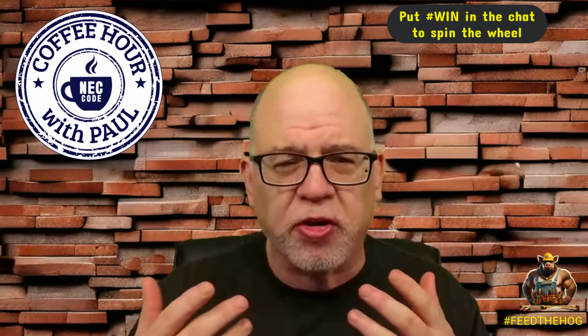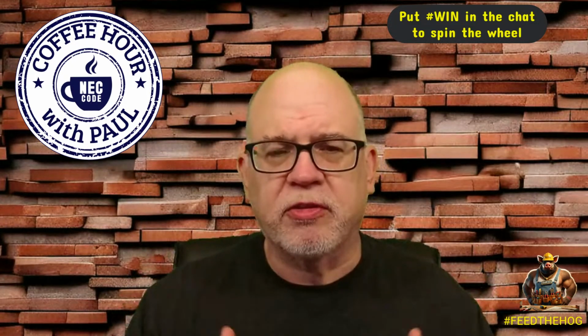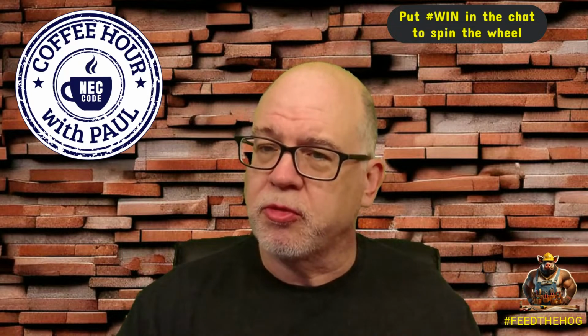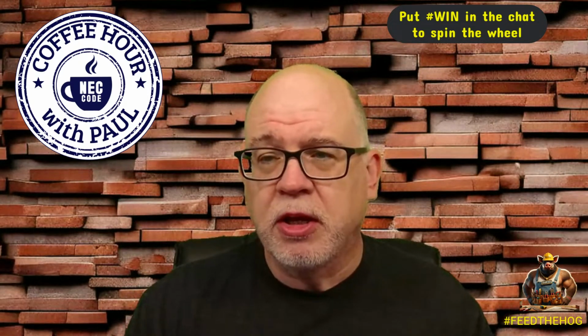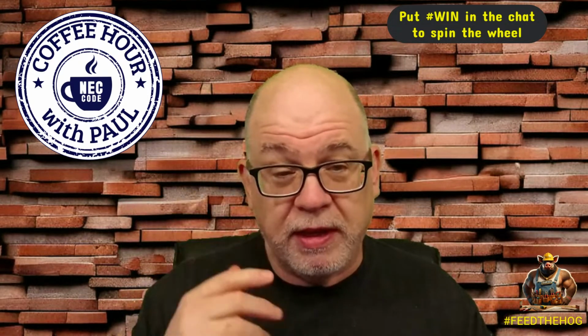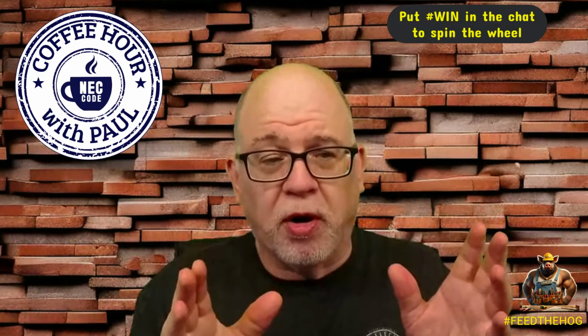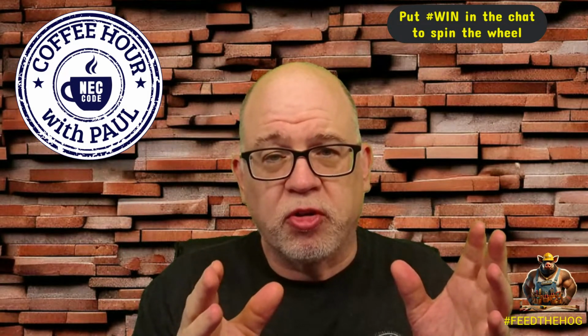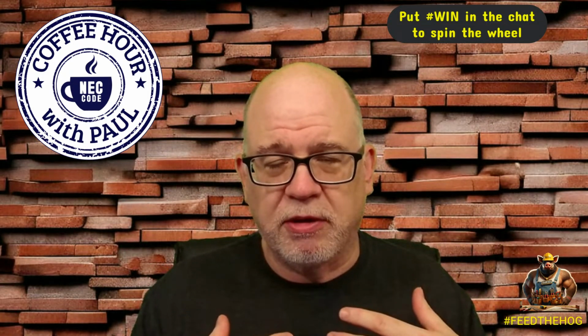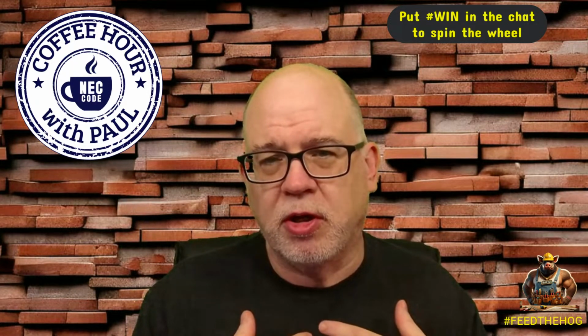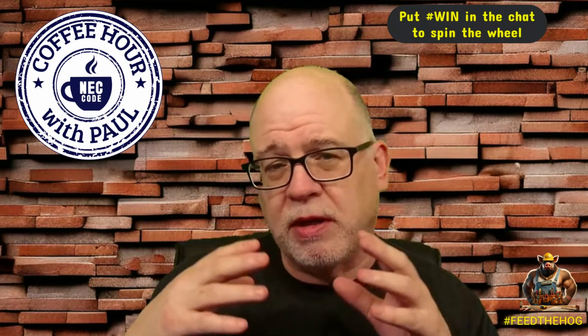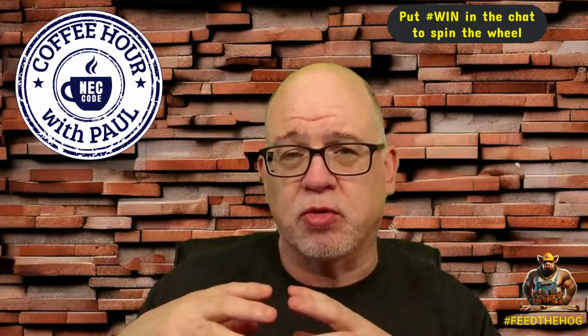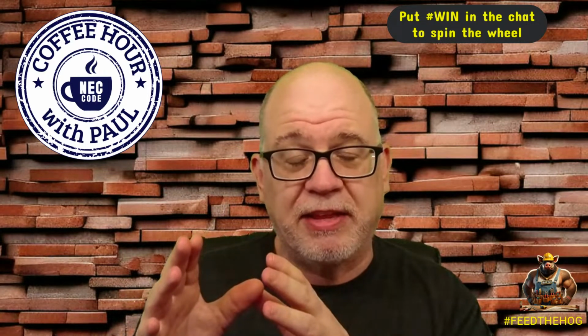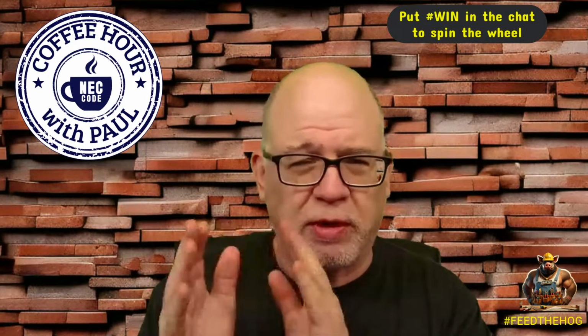But there was no other rule in there that's going to give you a break when it comes to the lighting. And the other issue is you're never going to have the multifamily where the commercial part of the building is going to do anything within your individual dwelling unit. That would be a violation in the National Electrical Code because your individual dwelling unit can only supply loads that are in your individual dwelling unit, right? Not outside that dwelling unit. So I think it's like 210.25 or something.